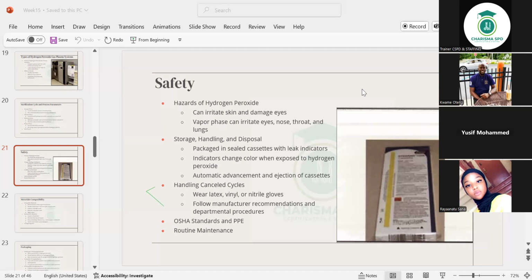That is a good sterilant. It takes shorter time compared to the ETO. So it's good for us to use. It comes in a sealed cassette, as I was telling you. The image that you see on the slide is the cassette within that wrap. You see that yellow line on it. In case there's an exposure where there's a leakage, that yellow line will change from yellow or white to red. You see that yellow line on the package? Yes. The cassette is within it. It's a plastic cassette with several slots of hydrogen peroxide in there.